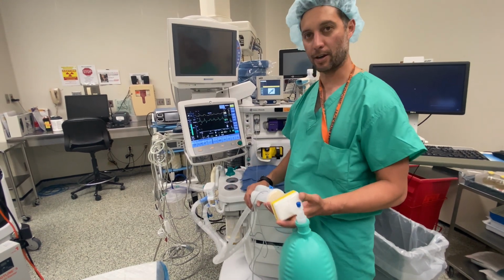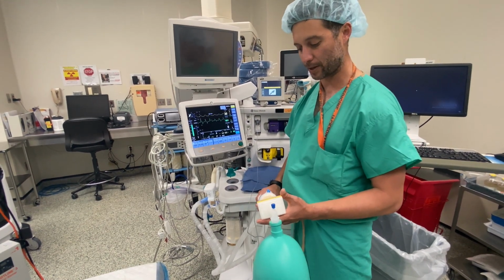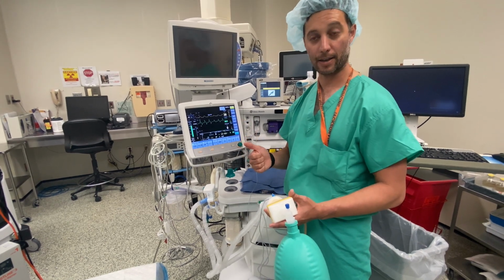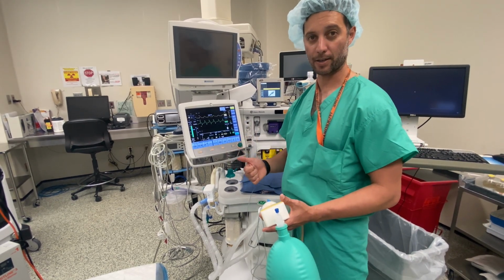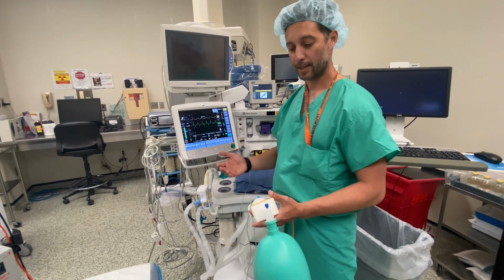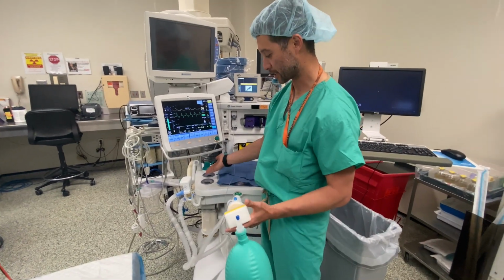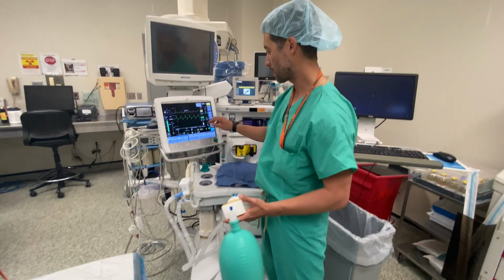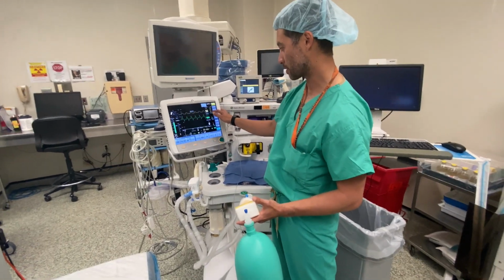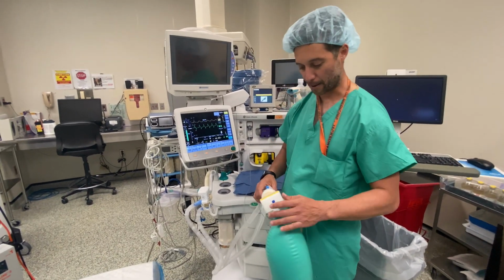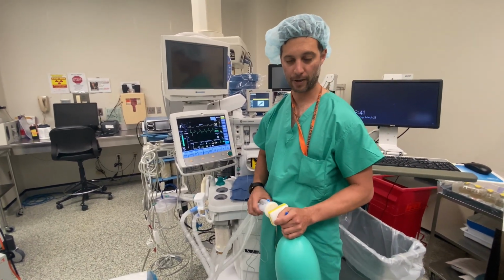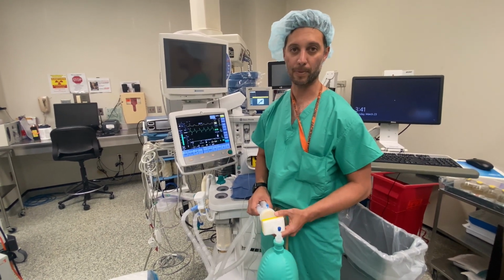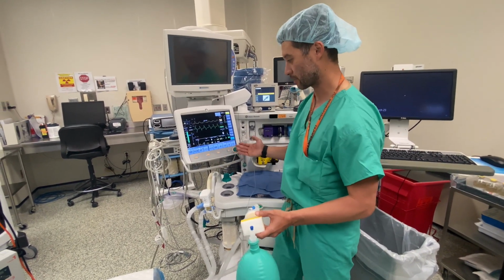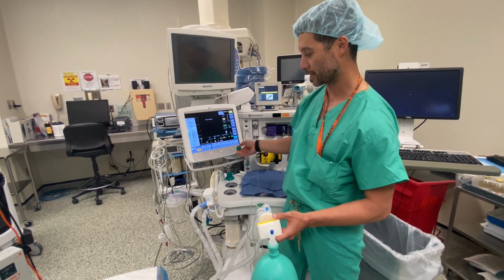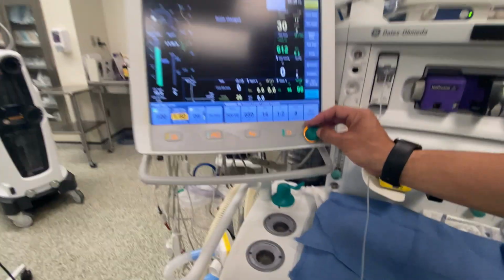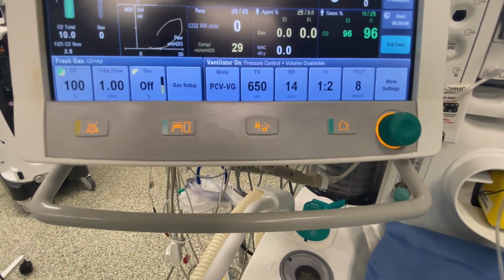If you find yourself in austere circumstances and you had to use an ICU ventilator, the first gotcha that you'll figure out is that there's no waste gas or scavenging pipeline to hook that up to. The second thing that you'll find out is that by disconnecting the scavenging bag, you'll be able to maintain normalization of PEEP as we've decided here. Another main difference between anesthesia machines and ICU ventilators is that ICU ventilators have the ability to introduce humidity. And we, in anesthesia, do that naturally by lowering the flow rate from, say, 10 liters down to, say, 1 liter or so. So that's what we're doing here.